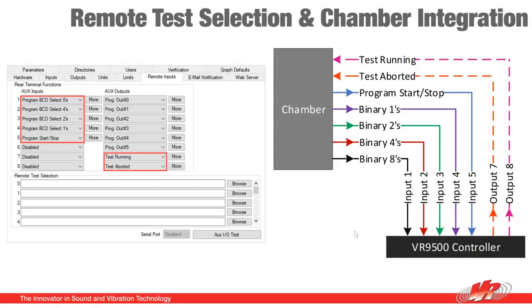Here we have remote test selection and chamber integration. This uses a binary control device or a binary output from the chamber to remotely select tests and start and stop them. Now I have my remote I/O demonstration board connected so that I can demonstrate these features.